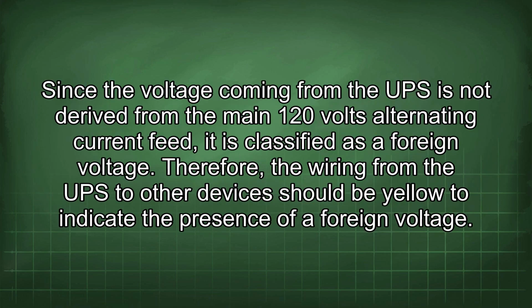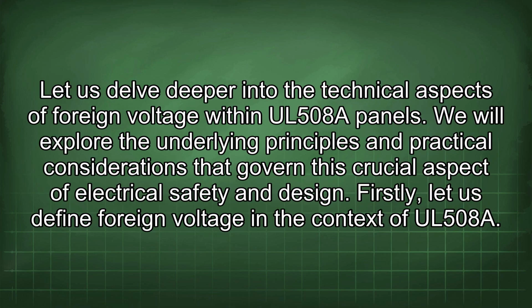Since the voltage coming from the UPS is not derived from the main 120 volts alternating current feed, it is classified as a foreign voltage. Therefore, the wiring from the UPS to other devices should be yellow to indicate the presence of a foreign voltage. Let us delve deeper into the technical aspects of foreign voltage within UL508A panels. We will explore the underlying principles and practical considerations that govern this crucial aspect of electrical safety and design.